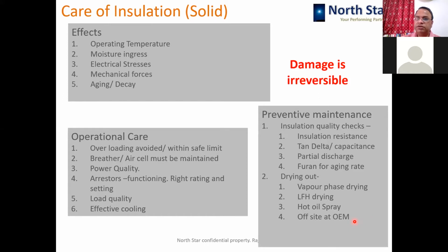How do I know that my insulation has been affected by moisture? One way is to check the PI of the transformer, and tan delta and capacitance and resistance tests can give us the condition of the insulation, but that will not necessarily be because of moisture. Moisture is one of the factors, but based on the operating condition, we can infer that it can be because of moisture.